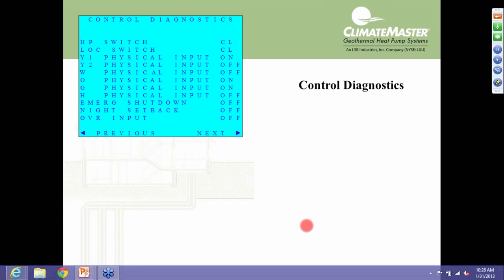Now, in control diagnostics, this first screen shows any physical inputs, and it also shows you if your high pressure switch and your loss of charge switch are either open or closed. Obviously, if they are open, we're going to have to correct that first before we do anything.